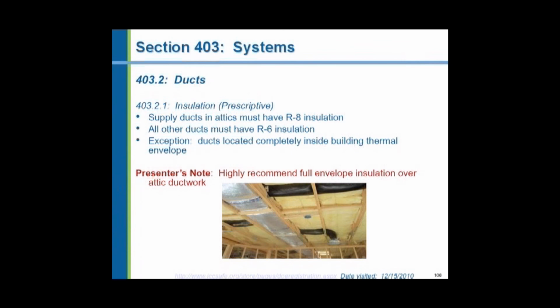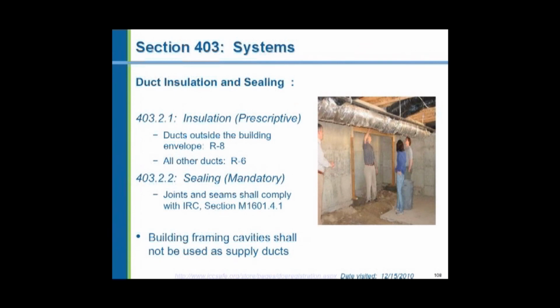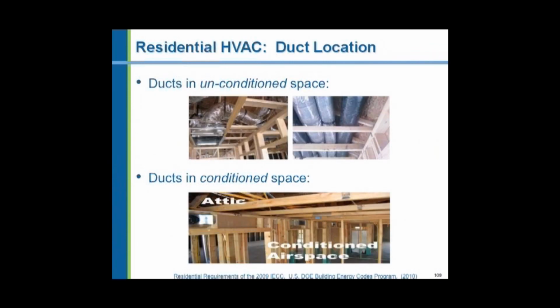Ductwork outside the building thermal envelope must be insulated. Supply ducts to an R8 insulation thickness, return ducts to an R6 insulation thickness. Building framing cavities can be used as return ducts. Remember, we pan across a couple of joist spaces to create a return duct in the basement? We can still do that. However, we cannot use building cavities as supply air ductwork. Here's an example of ductwork being installed above a ceiling, an insulated ceiling.